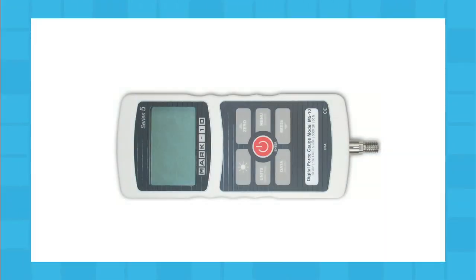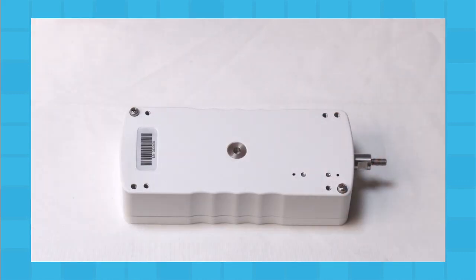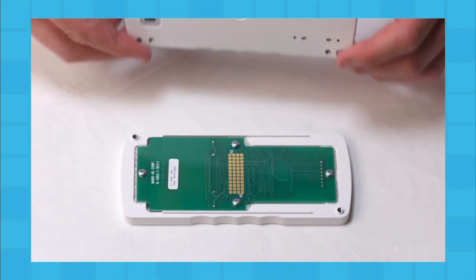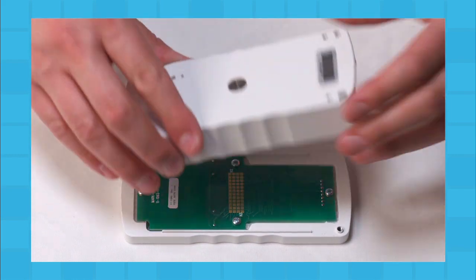To accommodate handheld or test stand mounting, the orientation of the load cell shaft may be flipped while the keypad and display remain upright. To reverse the orientation, separate the two halves of the housing, reverse, and reassemble.